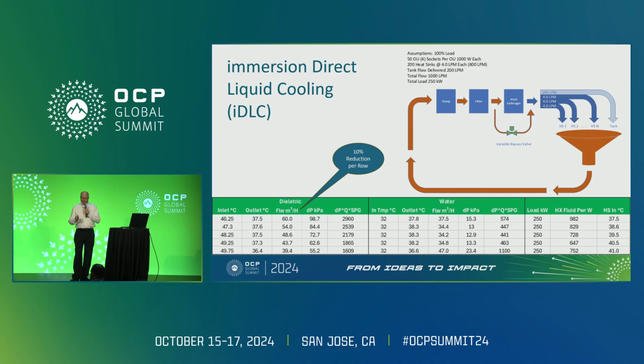But now let's push this thing a little bit further out. And here's where things start to say, well, you know what? There may be something here. We've done a whole lot of different scenarios, and I could show you some that are even more optimistic and some that are worse. So I took the lower 30% up to the upper 80th percentile of performance improvements. Here you can see that as we begin to do this bypass scheme, we're going from 982 watts down to 647. So we're shaving off over 300 watts by bypassing the fluid flow. We're still able to get to a mixed temperature very close to the original target, and we let that float around a little bit, as I mentioned.